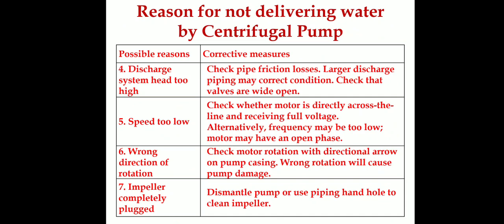The fifth cause is speed too low. The electricity supply may have fluctuations in voltage, current, and frequency, causing speed variation in the motor. We have to ensure proper voltage and current regulation to maintain correct pump speed and water delivery.